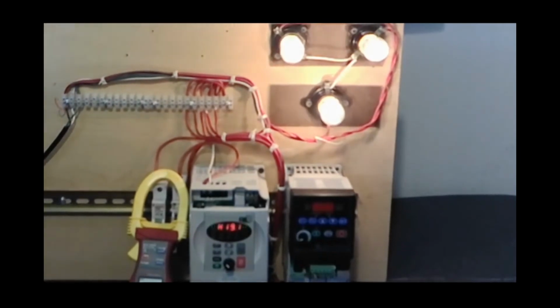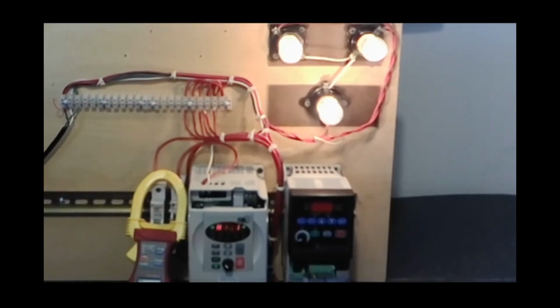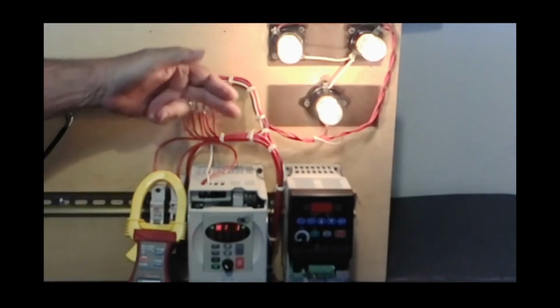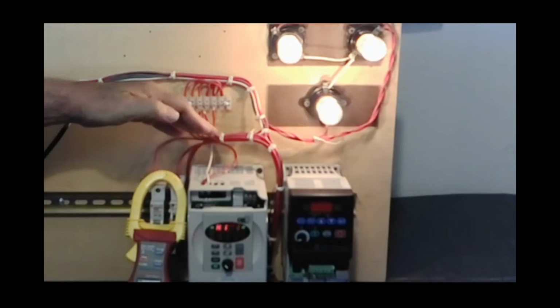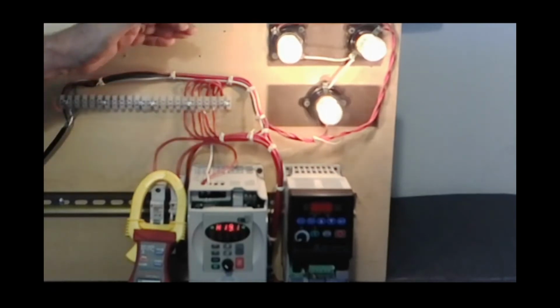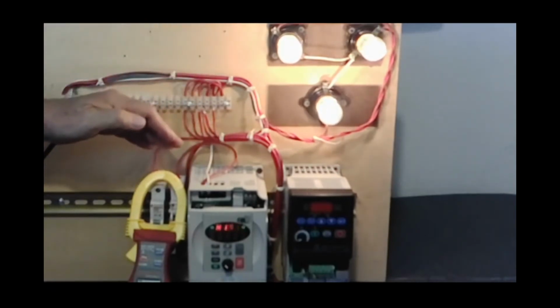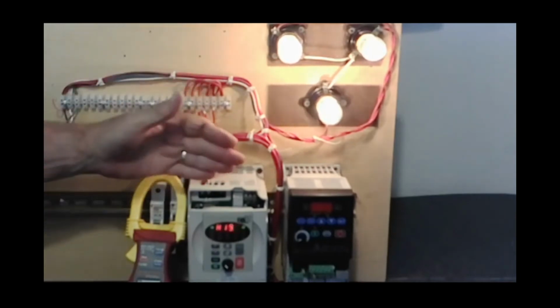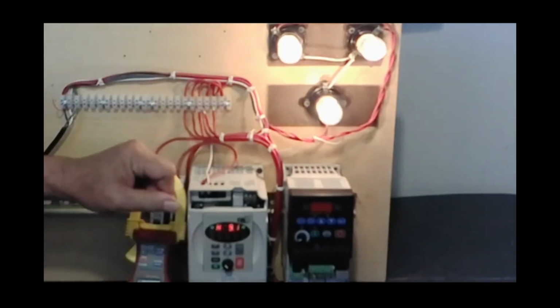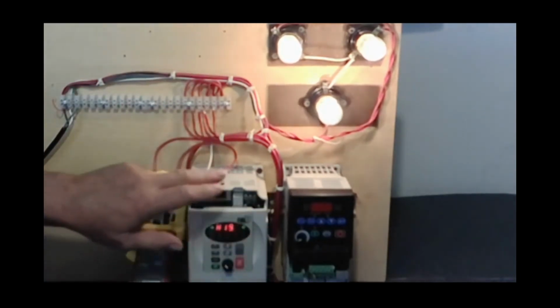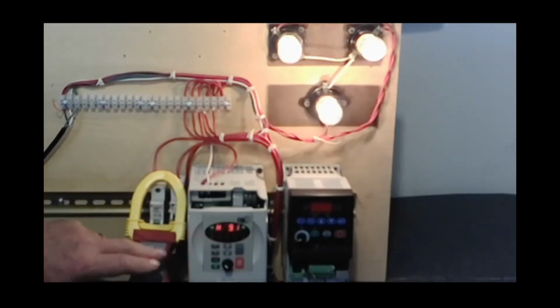There's terminals right there that tell me it has to have a voltage applied to a certain terminal to run. So there's different methods in which the drive can be troubleshot. The output is probably the first most common, to make sure you got an internal voltage that is going to be the same in all three phases. If you have differences there, then the problem is going to be internally. Something internally within that drive is failing or has failed.